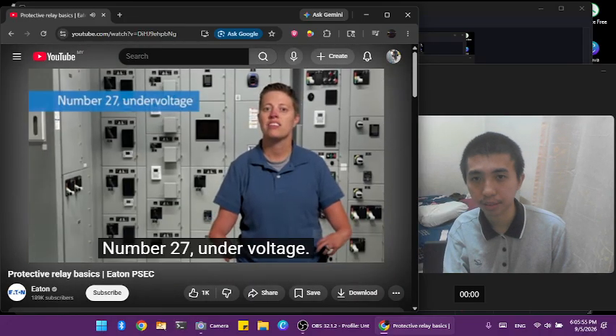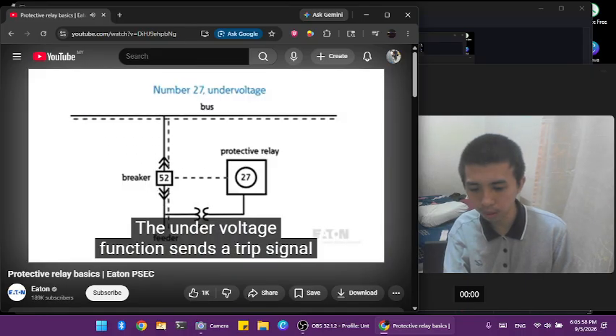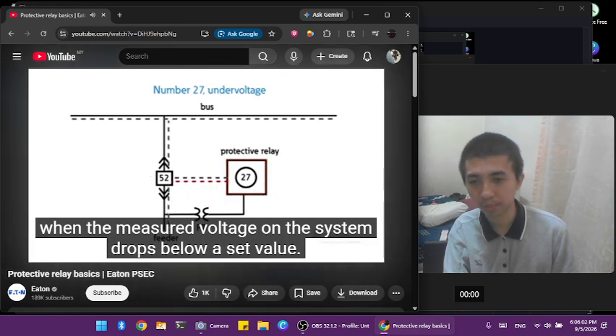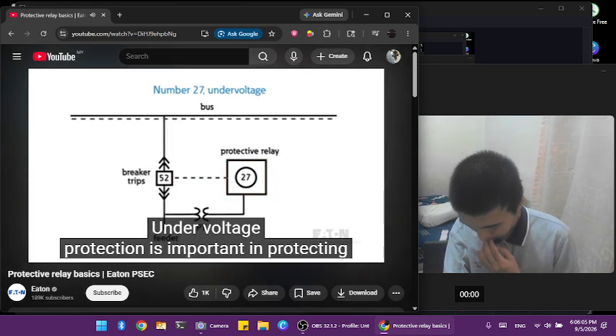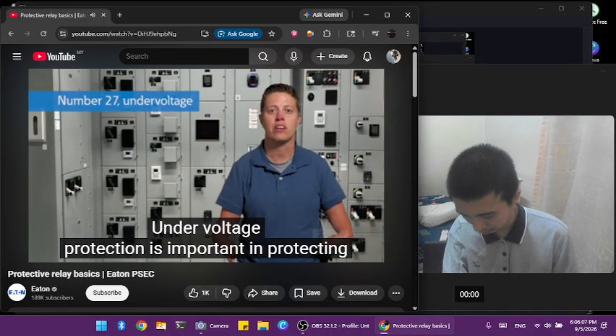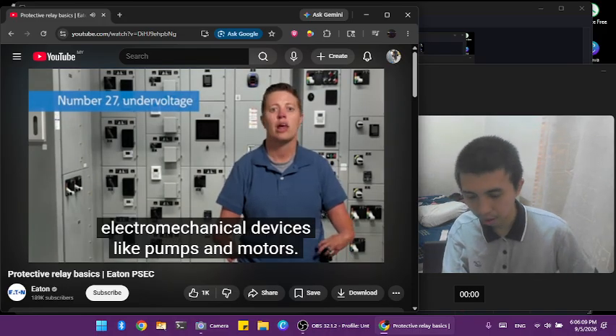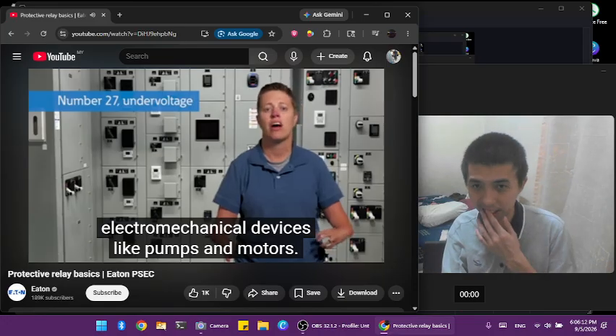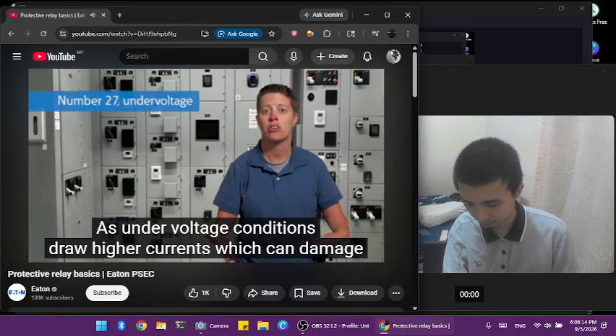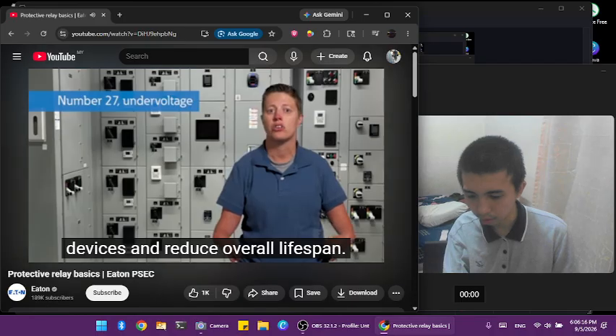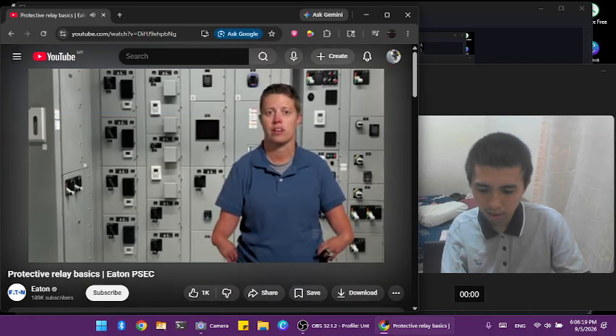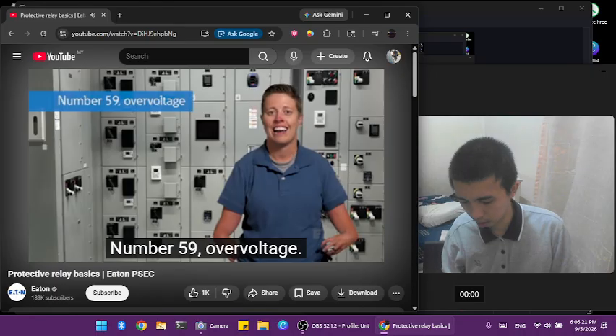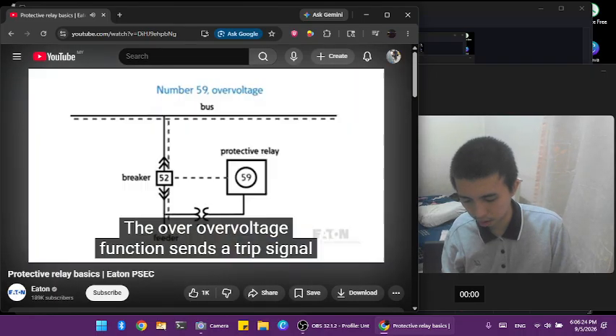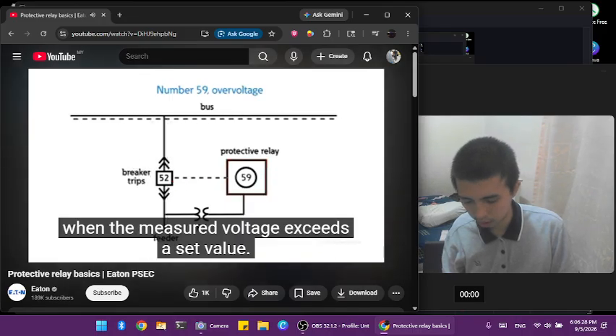Number 27, undervoltage. The undervoltage function sends a trip signal when the measured voltage on the system drops below a set value. Undervoltage protection is important in protecting electromechanical devices like pumps and motors, as undervoltage conditions draw higher currents, which can damage devices and reduce overall lifespan. Number 59, overvoltage. The overvoltage function sends a trip signal when the measured voltage exceeds a set value.